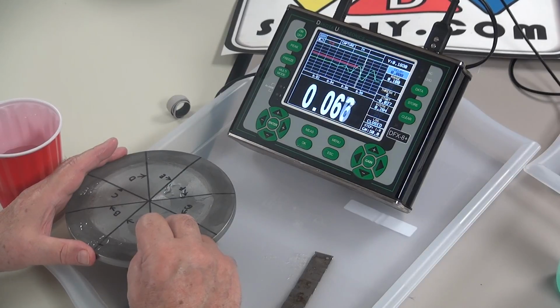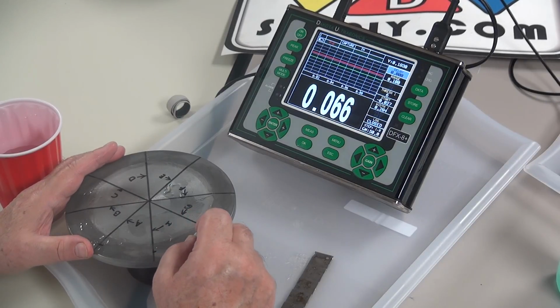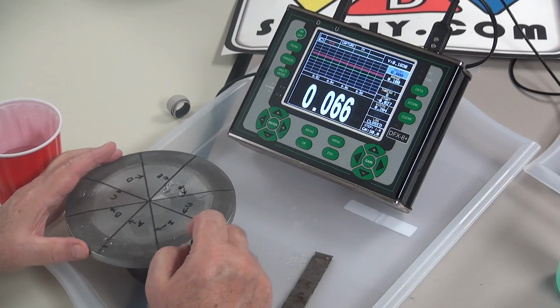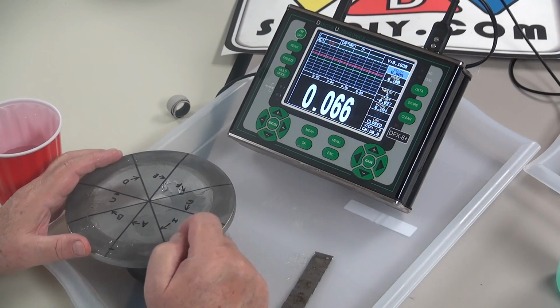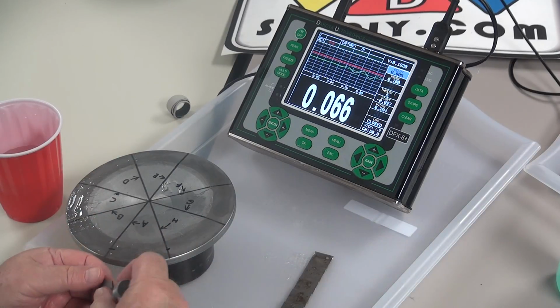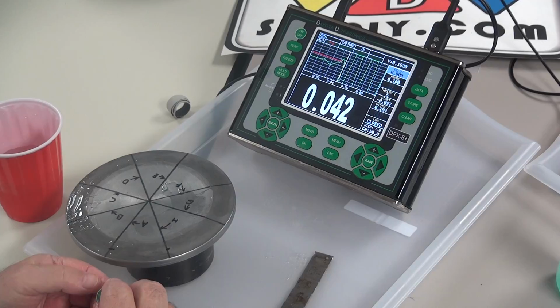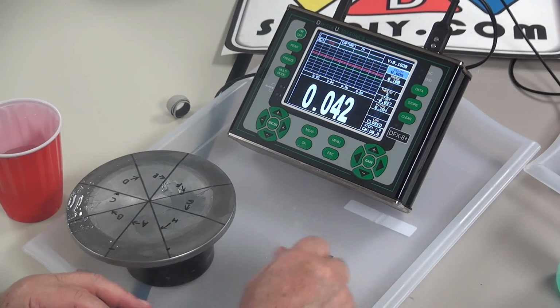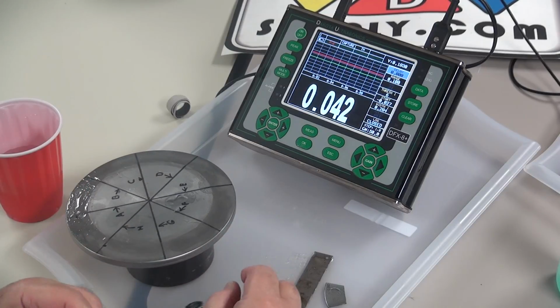Our calibration is using shims of tungsten of known thickness over air. And obviously we have tungsten to moly. The difference is significant both in signal amplitude and in the phase of the signal. The phase of the signal actually reverses over the moly, so we have to change the gate setting from negative to positive when we go to the actual sample. Sectioning the sample, creating some actual knowns to calibrate to will improve the situation.